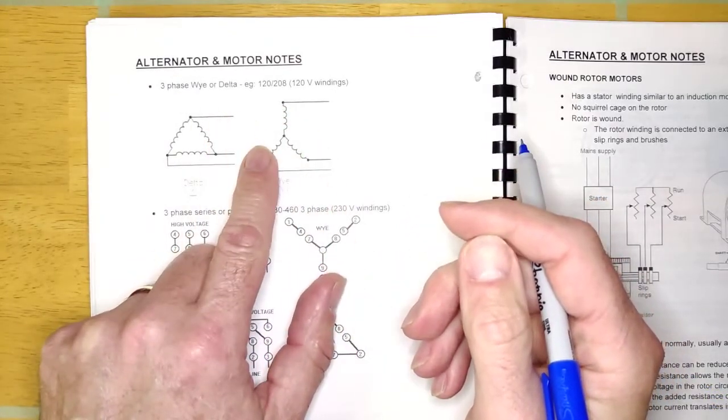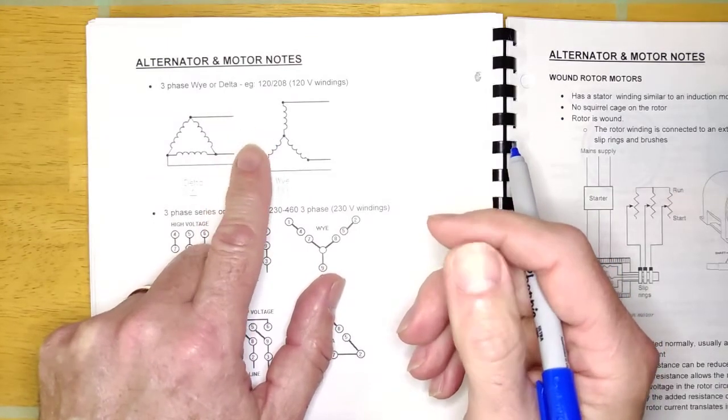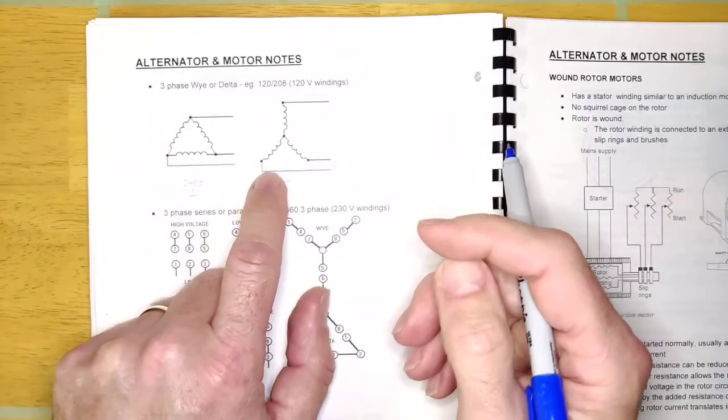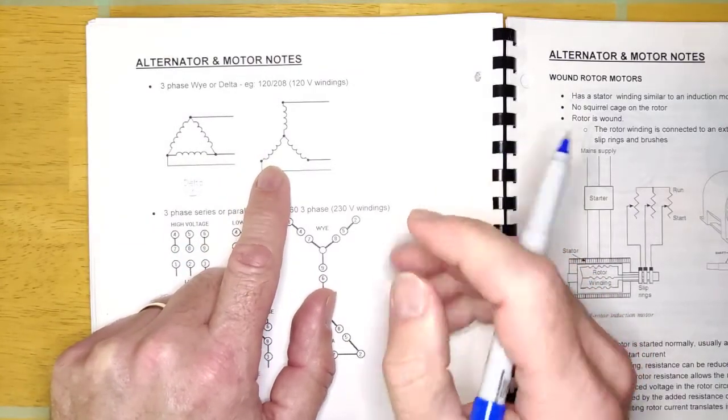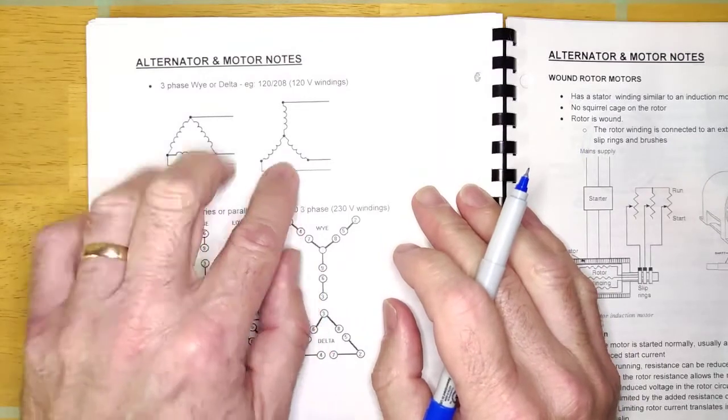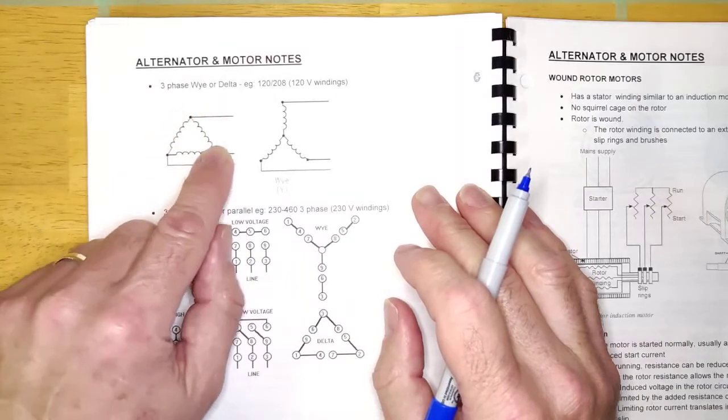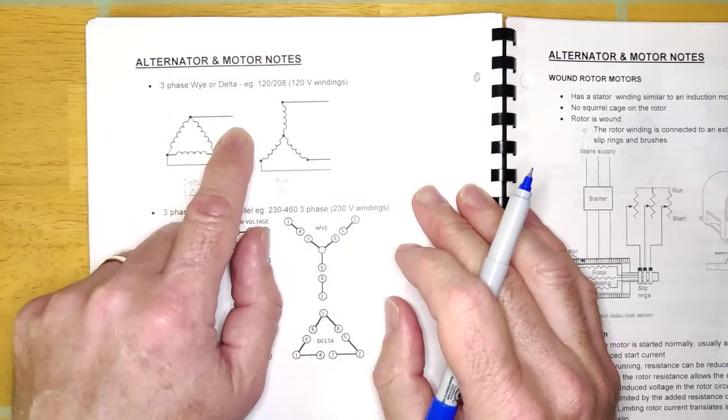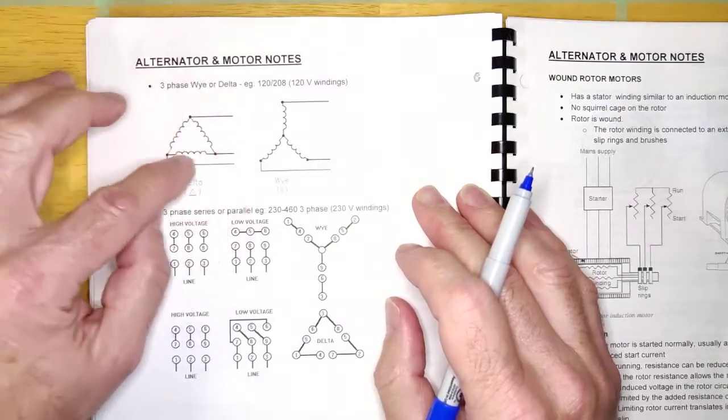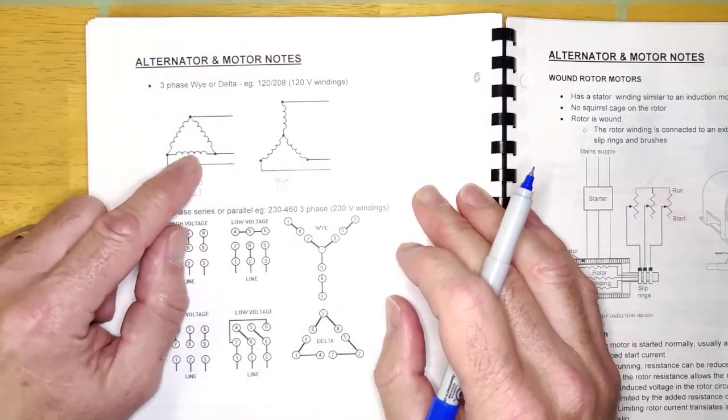So this is a 120 208-volt motor, and you're changing the voltage by changing the winding configuration. Now, I just want to say about this that this is never done or very rarely as far as I know. But it is done for the purpose of low reduced current starting. So if you have a Y delta-connected motor, so let's say this was a 600-volt motor, and you would have 600 volts here.